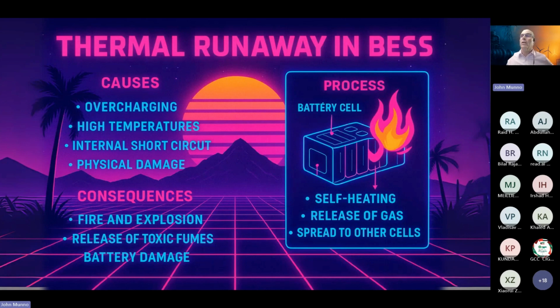I'll mention that I was at a conference a few months ago and Tesla was there. And Tesla announced that they use a sparker system where they install about 10 or 11 sparkers, igniters, in the battery containers. The purpose of these sparkers is to ignite the combustible fumes, the gases, before they reach a point which could cause an explosion that would damage the container. So by having this continuous presence of sparks, they eliminate the potential for an explosion. It's a very interesting approach.